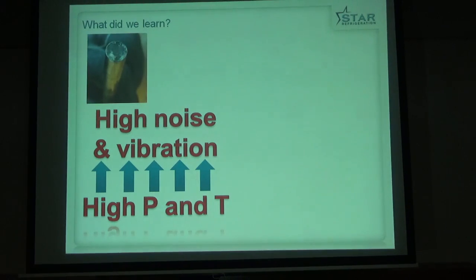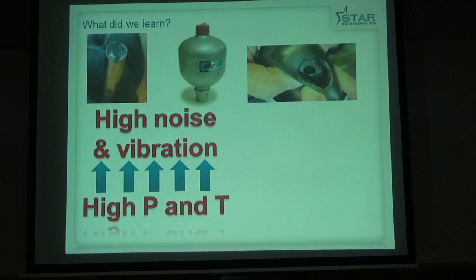Also high noise and vibration. The vibration also caused some components to break. We fitted HYDAC style dampers to the hydraulic circuit to reduce the vibration. This was a great result, very positive. But the rubber of the bellows of the damper wasn't compatible with the ammonia, so we had to think again.